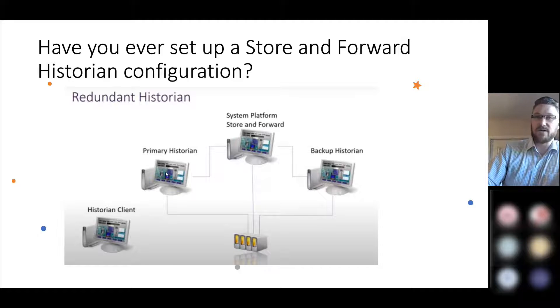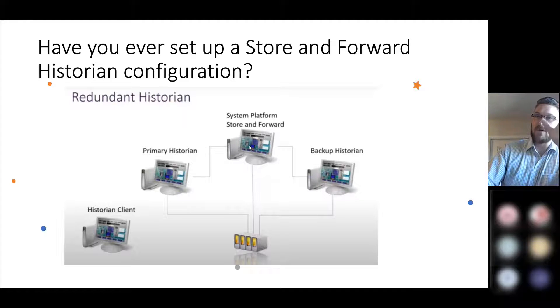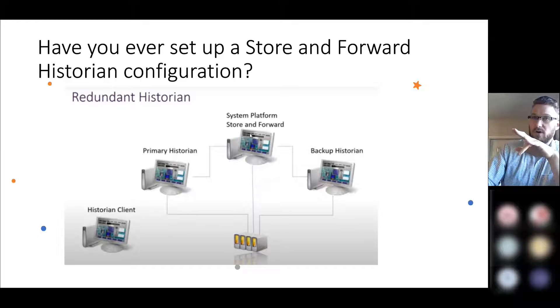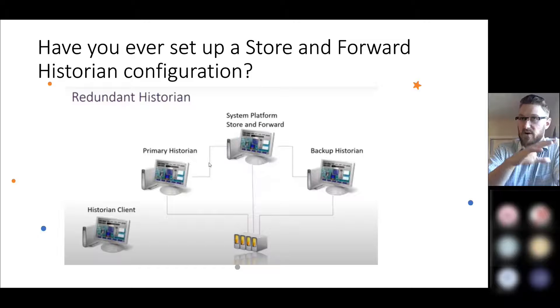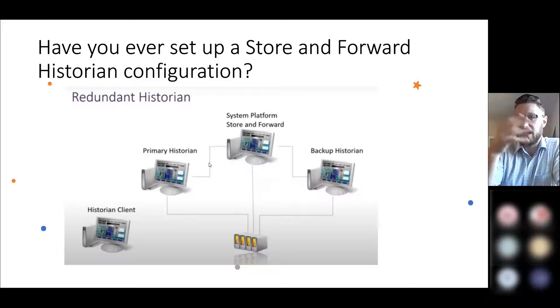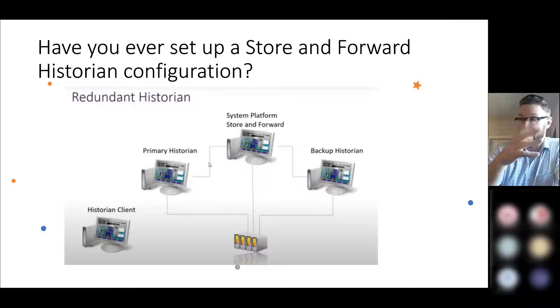So if you lose the connection between your primary Historian PC and your System Platform PC, that's okay — it's not as if you're going to permanently lose data. What will happen is your System Platform PC will begin to store that same data until the connection to your primary Historian PC is brought back online. This can be really useful if there are breaks in your connection — a cable gets unplugged, the network goes down temporarily — your System Platform PC will continue to store that data until the connection is renewed.